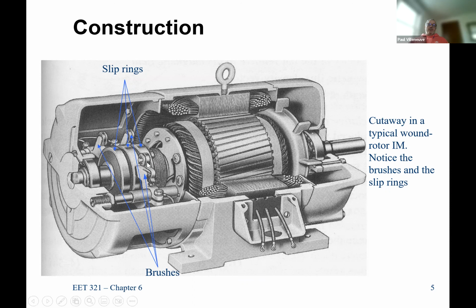And the reason you do this is because, remember, this is carbon. Carbon is very soft, and that's a good thing because you want the carbon to wear down. You don't want this slip ring to wear. Nothing is perfectly polished. Over time, there's going to be some wearing of this carbon brush because this slip ring is not perfectly milled. You're going to have some resistance. And I want to replace the carbon brushes way before I replace my slip rings. If you take a look at older cordless drills or something like that, if you plug it in, sometimes you can see some sparking if it's an older drill. That's because the brushes on there have started to pit to the point where you're getting some arcing between the stationary part and the rotating part.